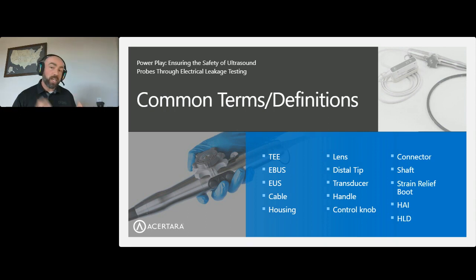Typically on general and endocavity probes, the probe is handled by the housing. In TEE probes, most of the housing and the insertion tube are going to be inside the patient. And so the control housing is typically where the anesthesiologist or whoever's actually using the TEE probe is going to handle that probe, and that's where there's typically buttons to be able to steer. You might see these in the image here on the left.